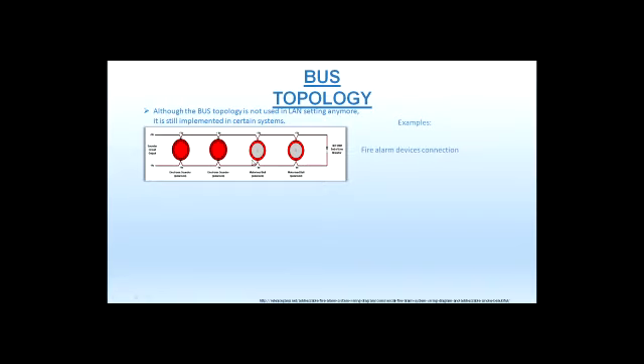If you break the line at some point, the zone won't see the end of line resistor, but it also won't see a dead short, because the line is open. It won't trigger as a fire alarm, but it will trigger as a trouble on the line — that's when you hear the trouble buzzing. It's a very annoying buzz, and its purpose is to annoy the people in the building so they pick up the phone and call the service company, because something is wrong with the system and it may not be working properly.